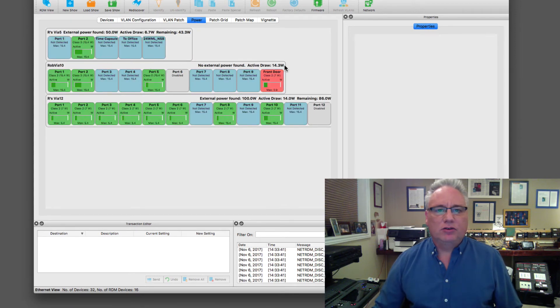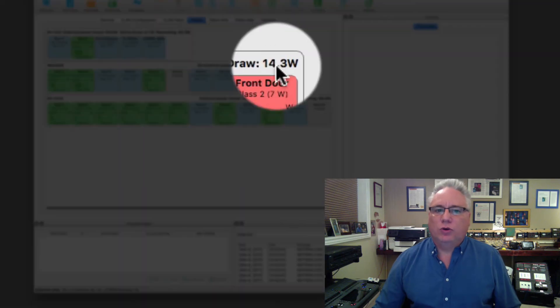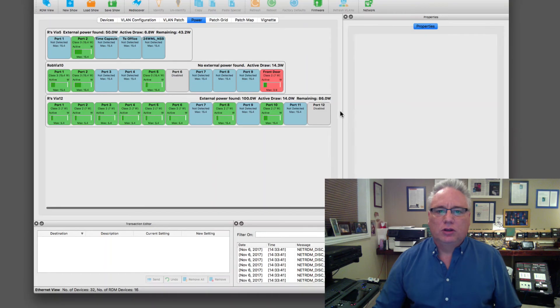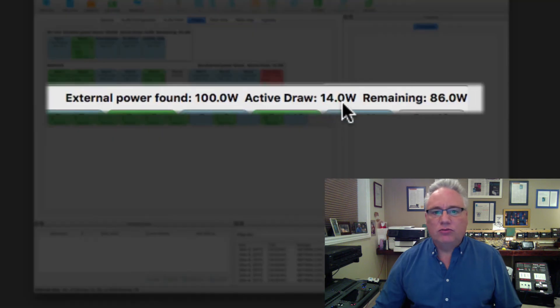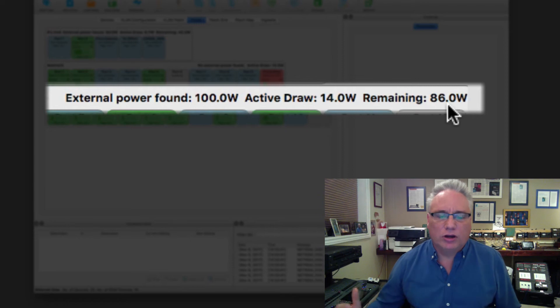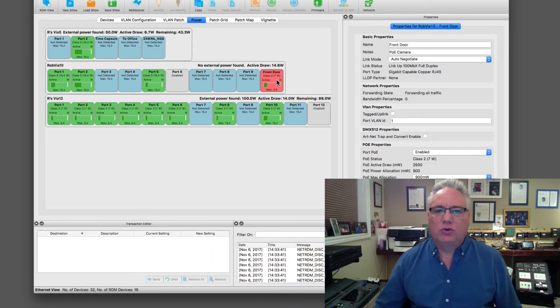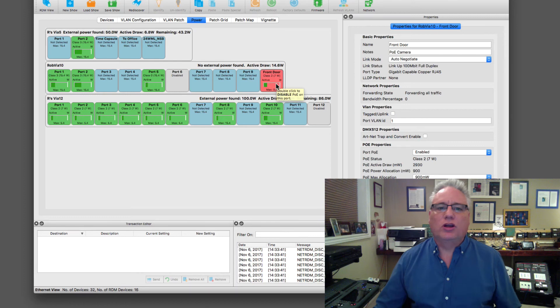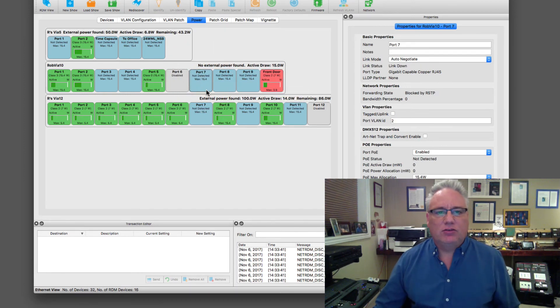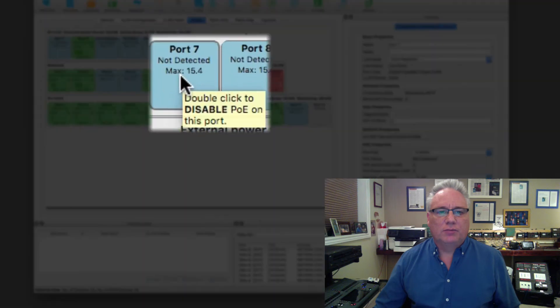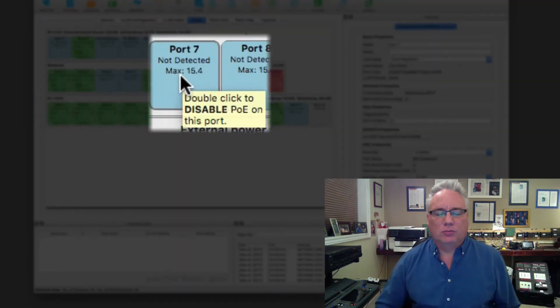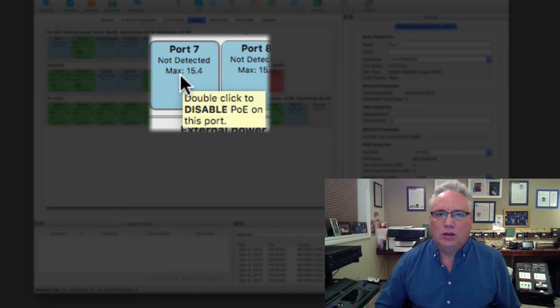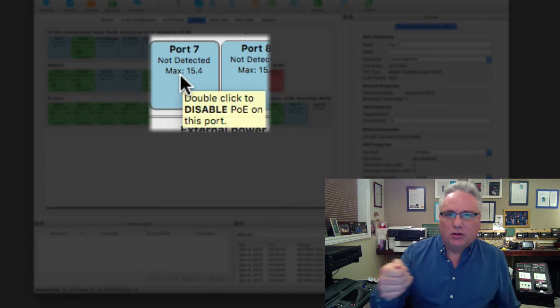We can also monitor the PoE power coming from the via. Right now the active draw on the via 10 is 14 watts in total, and on my via 12 there's 14 watts with 86 available because there's a 100 watt external supply. This guy here, the front door, is actually going above its allocation and that's why it's in red. It's really handy, you can just double click on a device and turn off its PoE, and that can recalibrate a device in the field without you physically having to go and unplug things.